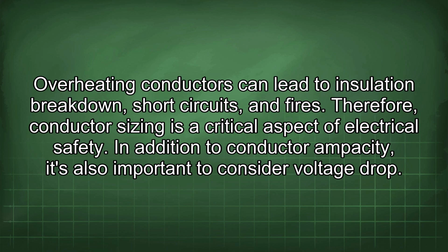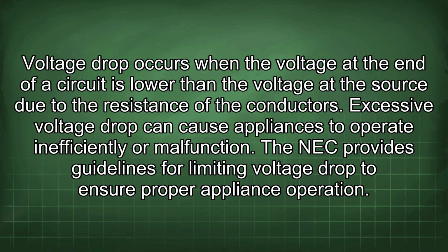In addition to conductor ampacity, it's also important to consider voltage drop. Voltage drop occurs when the voltage at the end of a circuit is lower than the voltage at the source due to the resistance of the conductors. Excessive voltage drop can cause appliances to operate inefficiently or malfunction. The NEC provides guidelines for limiting voltage drop to ensure proper appliance operation.